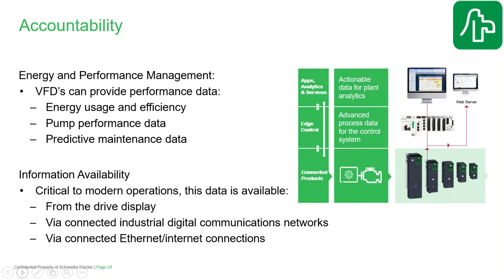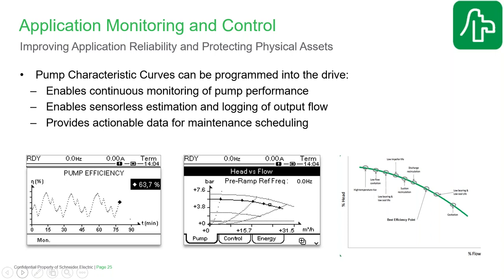And that information is available in multiple ways. You can get it from the drive itself. If you have a communication network to a control system, you can hook it up through any digital communication protocol, just plug in the right module for that comm system. All the drives as standard have Ethernet inputs with a built-in web server. What sort of things can you get out of it?